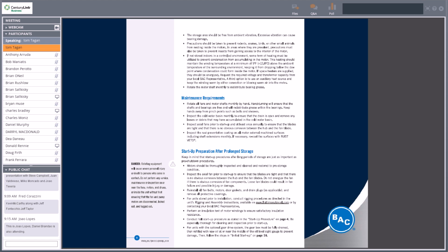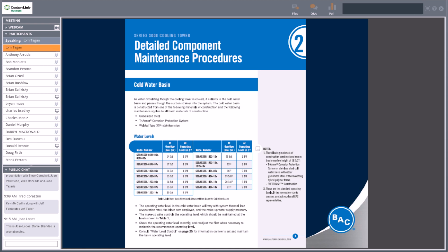Maintenance requirements, startup after preparation, again, very similar to the startup if it was a new job. Inspect the fans, you're going to bump the fan motor, check the rotation, adjust the belt drive, you're going to fill the tower and clean it. Okay, so here's where it gets into some of the detailed procedures that are recommended on that first page. Checking your water levels. The O&M manuals will give you the recommended operating level, whether it's a distribution, for the distribution basin in this case.